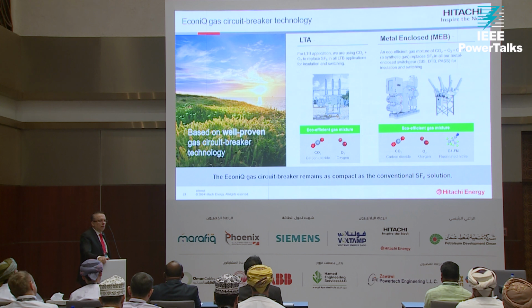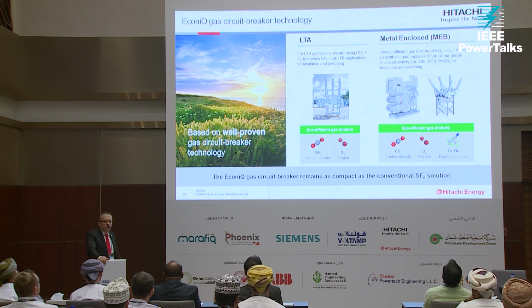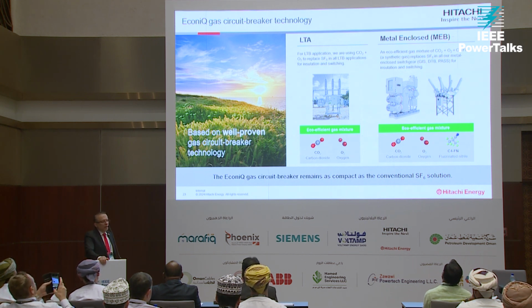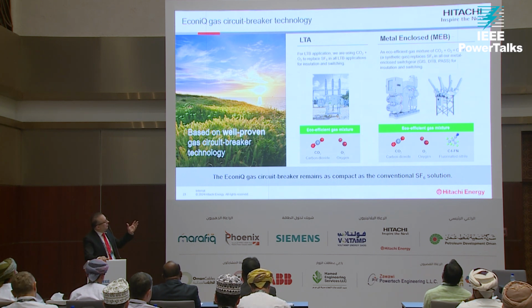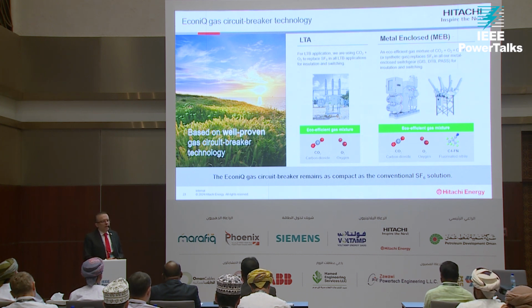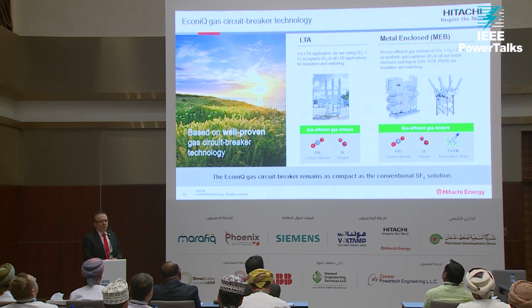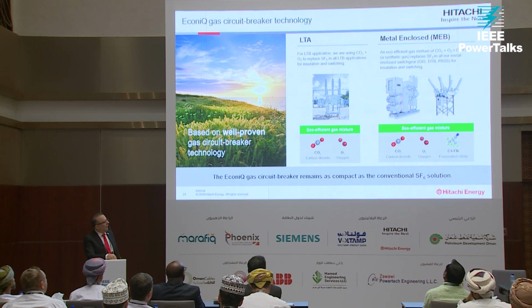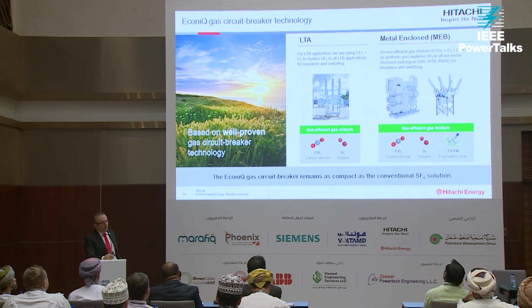You might ask: again we're using CO2, but compared to the SF6 that was there before, which had a GWP of 23,500 times more effect on global warming, our new solution using the same amount of gas has exactly the same footprint. So practically the amount of gas we use is more or less the same, but the effect of leakage on global warming, comparing the old SF6 solution to the new one, is 23,500 times less, and more or less the same improvement applies to the other solution.